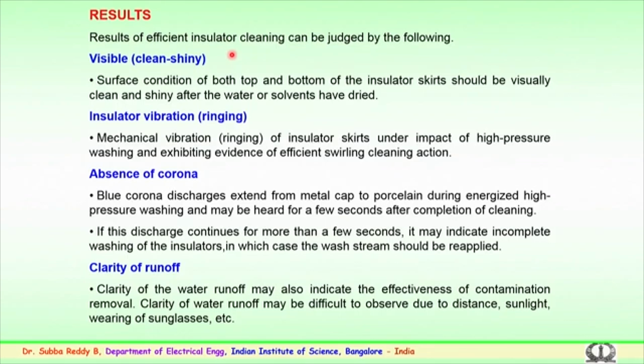How to judge the results of cleaning is an important decision to be taken by the personnel or technicians who do the cleaning of the insulators. How to check the efficiency of the cleaning can be judged in the following ways. One is visible through the naked eye, where the surface should be very clean and shiny. The surface of both top and bottom of the insulator petticoats or skirts should be visually clean and shiny after the water or solvents have dried.